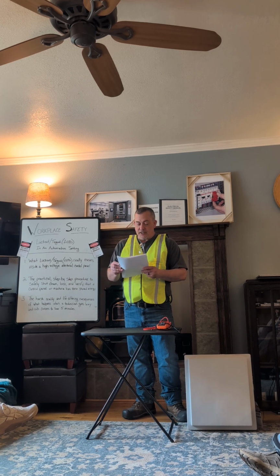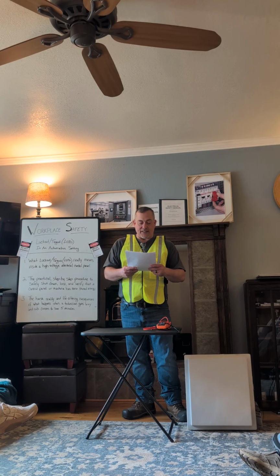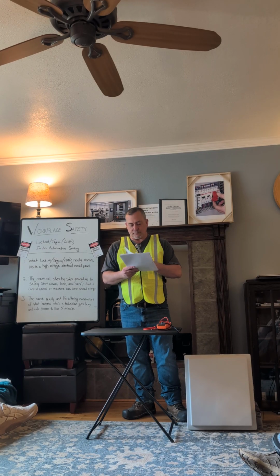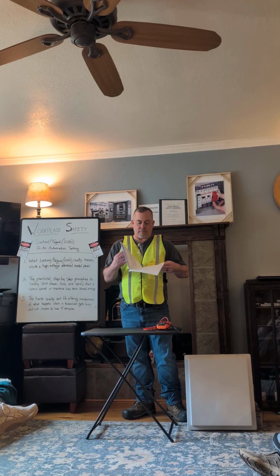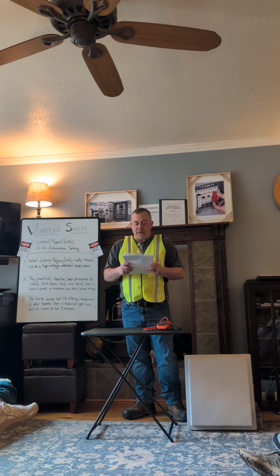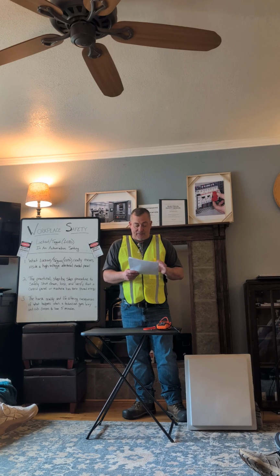These steps might seem redundant, but they are designed to protect against hidden failures. Verification of the voltage meter in steps 6 and 8 is critical because test leads can easily fail open. If they do, the meter probing a live circuit will read 0 volts, creating a deadly false sense of security. Following these 8 steps seems simple on paper, but failing to execute them has a massive tragic cost.